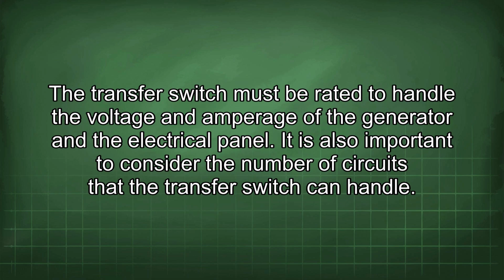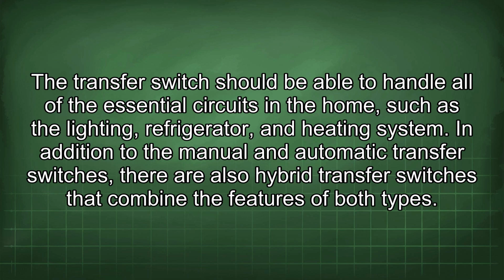The transfer switch must be rated to handle the voltage and amperage of the generator and the electrical panel. It is also important to consider the number of circuits that the transfer switch can handle. The transfer switch should be able to handle all of the essential circuits in the home, such as the lighting, refrigerator, and heating system.